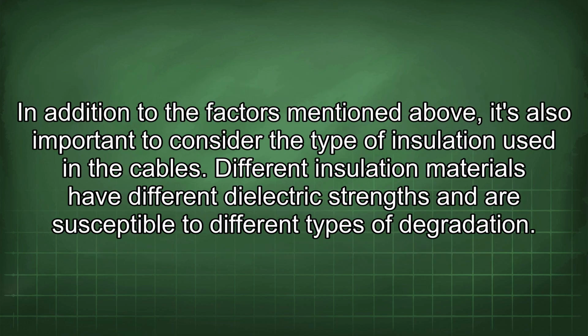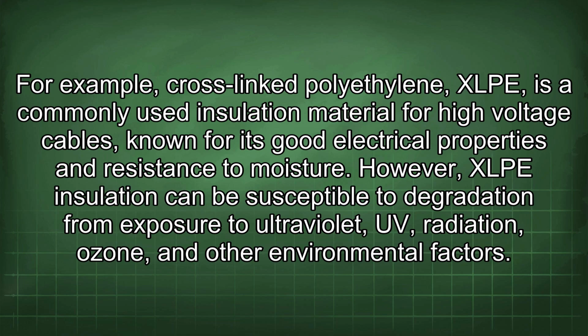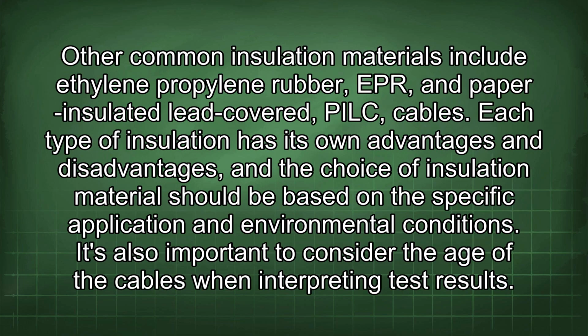In addition to the factors mentioned above, it's also important to consider the type of insulation used in the cables. Different insulation materials have different dielectric strengths and are susceptible to different types of degradation. For example, cross-linked polyethylene, XLPE, is a commonly used insulation material for high-voltage cables, known for its good electrical properties and resistance to moisture. However, XLPE insulation can be susceptible to degradation from exposure to ultraviolet, UV, radiation, ozone, and other environmental factors. Other common insulation materials include ethylene propylene rubber, EPR, and paper-insulated lead-covered, PILC, cables. Each type of insulation has its own advantages and disadvantages, and the choice of insulation material should be based on the specific application and environmental conditions.